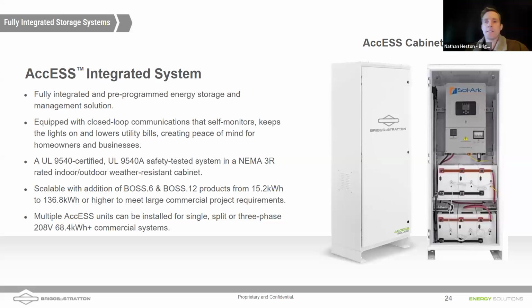Nathan, Daniel, what are we looking at here? Verlin asks, will the battery pack and the Sol-Ark handle the inrush current of an AC when running solely on batteries? The answer to you, Verlin, is that the battery can surge to 300 amps for a single stack. The Sol-Ark can double its power output for 10 seconds. So you can go from 12 kilowatts up to 24 kilowatts to get you going. And Daniel, correct me if I'm wrong, and I'm kind of hesitant to say this, I think it'll do 100 amps for 0.1 seconds.